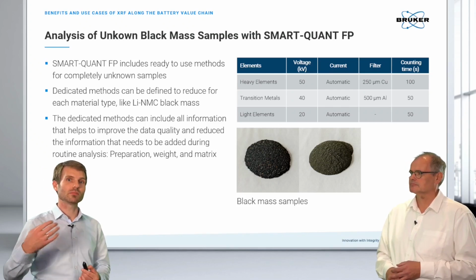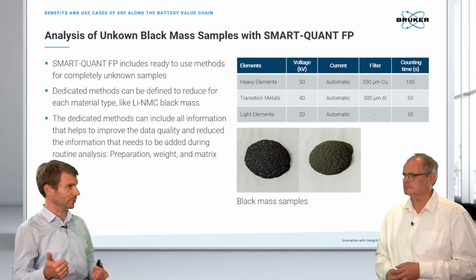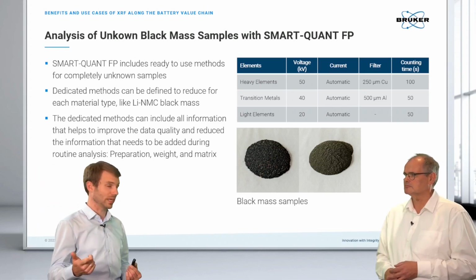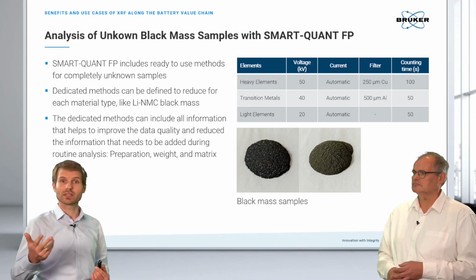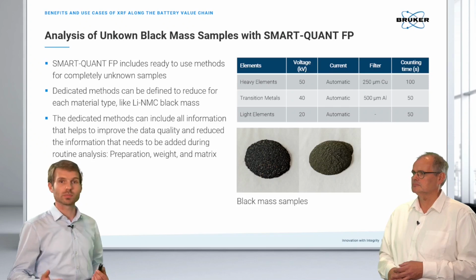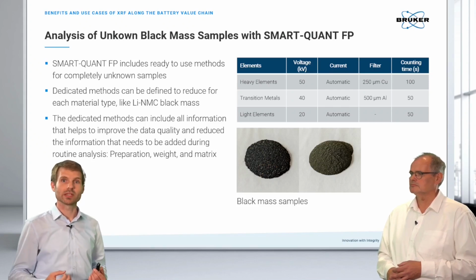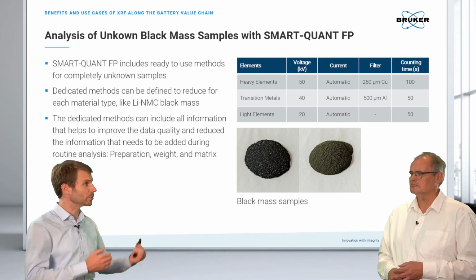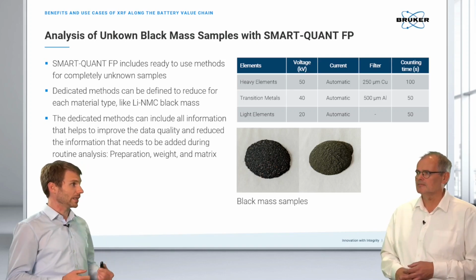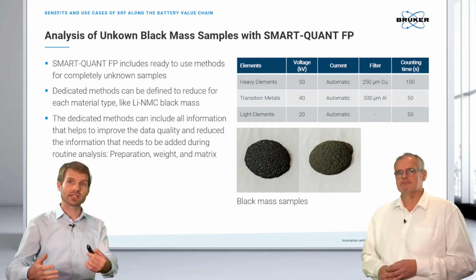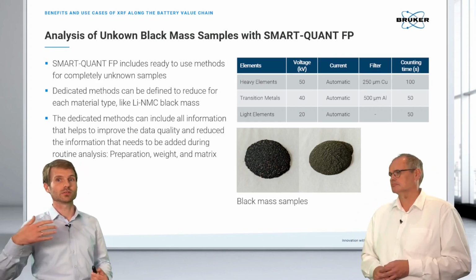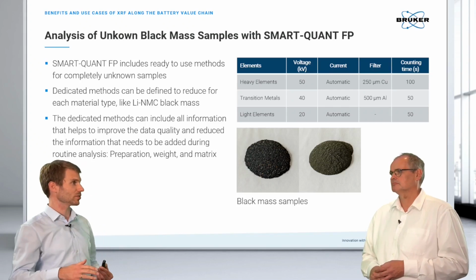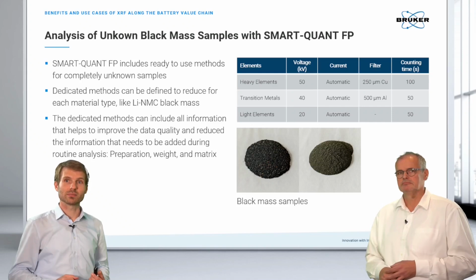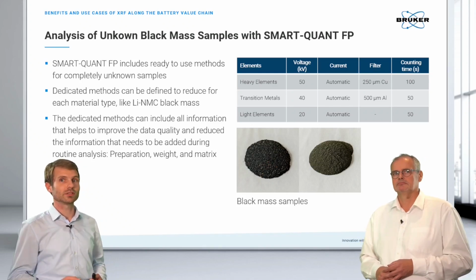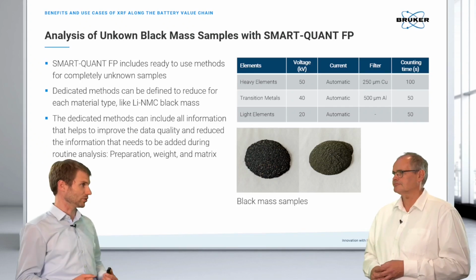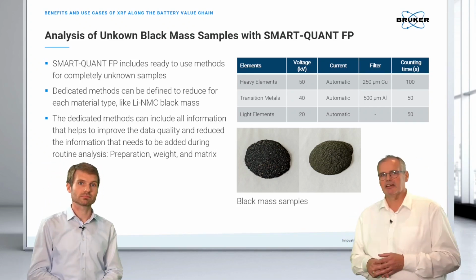SmartQuant comes with some ready solutions, for example, to measure oxide, smart matrix, but you can also fine-tune it. So you can give it some more information about your sample. So you tell it, for example, it's a powder, I added so and so much gram into the sample, and I know that in a black mass, for example, my matrix should be something carbon, so it should probably be graphite. If you enter that material, you will improve your data quality. But overall, the system really provides you the guidance of what to use. For example, to use for light elements rather low excitation voltages. It provides the best selection for the filter and also gives you a first indication about the counting times you should use.